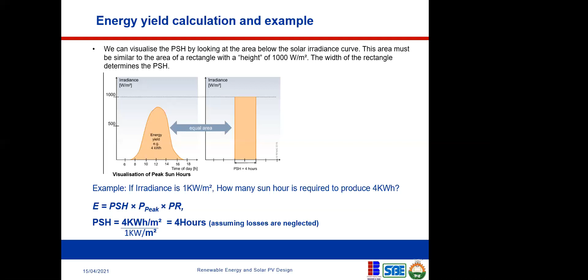So I was trying to cite an example here. If irradiance is 1 kilowatt per meter square, which is the same as 1000 watts, how many sun hours are required to produce 4 kilowatt hours? We want to calculate the sun hour, the same as the peak sun hour, required to produce 4 kilowatt hours. This formula is very important, and in this example we already know what the solar yield is.